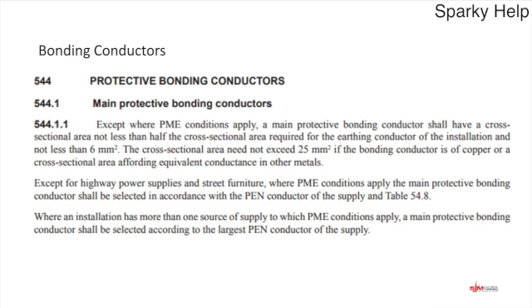So bonding conductors. We are talking about main protective bonding conductors within a building. So except where PME conditions, protective multiple earthing, which basically means TN-C-S, a main protective bonding conductor shall have a cross-sectional area not less than half the cross-sectional area required for the earthing conductor. So bonding, except where PME conditions apply, is based on the size of the earthing conductor, so not less than half of the installation and not less than 6mm. So the minimum size you can get away with is a 6mm within a building, providing it's not PME. The cross-sectional area need not exceed 25mm. Okay, so 6mm to 25mm is the maximum that you would like to see.